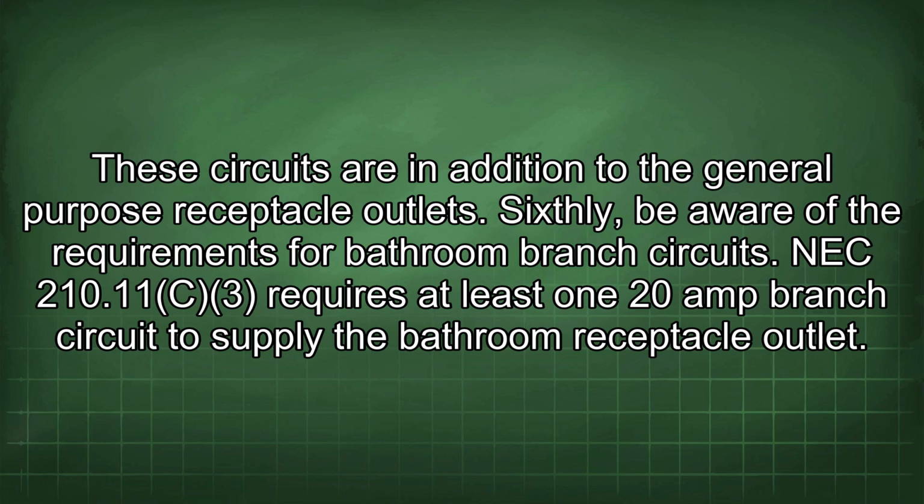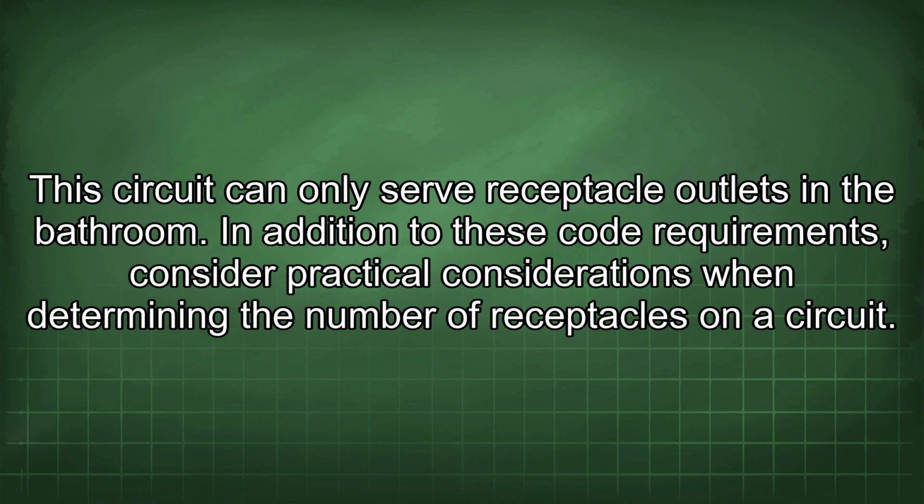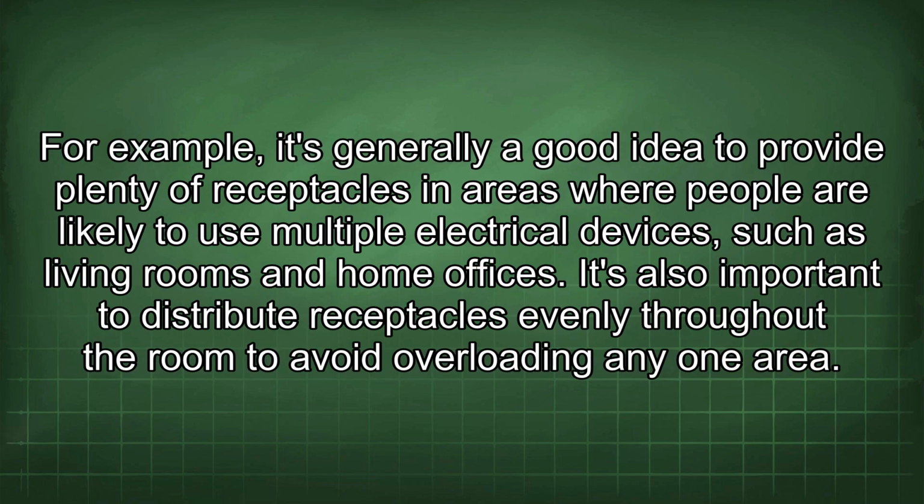Sixthly, be aware of the requirements for bathroom branch circuits. NEC 210.11(C)(3) requires at least one 20 amp branch circuit to supply the bathroom receptacle outlet. This circuit can only serve receptacle outlets in the bathroom. In addition to these code requirements, consider practical considerations when determining the number of receptacles on a circuit.